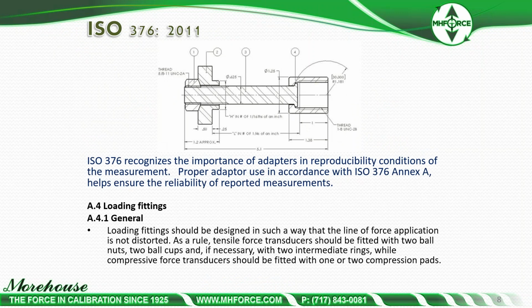And then here's the actual section from ISO 376 that recognizes the importance of adapters. This is the annex, A.4.1. Load fittings should be designed in such a way that the line of force application is not distorted. As a rule, tensile force transducers should be fitted with 2 ball nuts, 2 ball cups, and if necessary, with 2 intermediate rings, while compressive force transducers should be fitted with 1 or 2 compression pads. This is a good first step in establishing some type of standardization across the board, to say everybody should make these adapters.